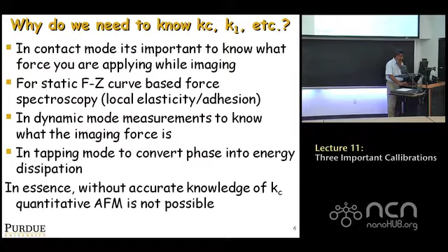Okay, so what are the different methods available for calculating stiffness? Many, many methods. NIST, the National Institute of Standards and Technology, has finally come up with a stiffness calibrating device, which is traceable to fundamental units. At NIST, they're very worried about every measurement being traceable to some fundamental unit, like the wavelength of light or forces, traceable standards. But this is not widely available. It's a MEMS device. Basically, you press on it, and it's a very well-calibrated MEMS device that just spits out the spring constant of your cantilever. But it's very expensive, it has to be used very carefully, and it's not available commercially.